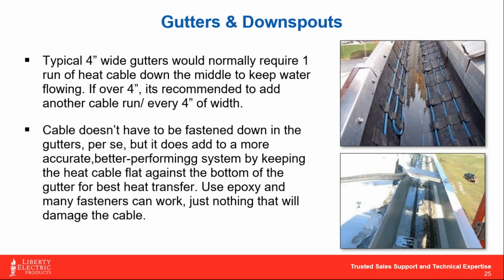That's the whole premise behind this: it's literally how far or how wide each of these has a melt path. Remember we talked about self-regulating cables having a life expectancy. Over time, you'll notice that melt path get thinner and thinner, until maybe you've got 10 years on that cable and you're only getting an inch per side melting. So those are some of the indices that tell you it's probably getting close to swapping out cables, or that you're losing a little power or heat output.